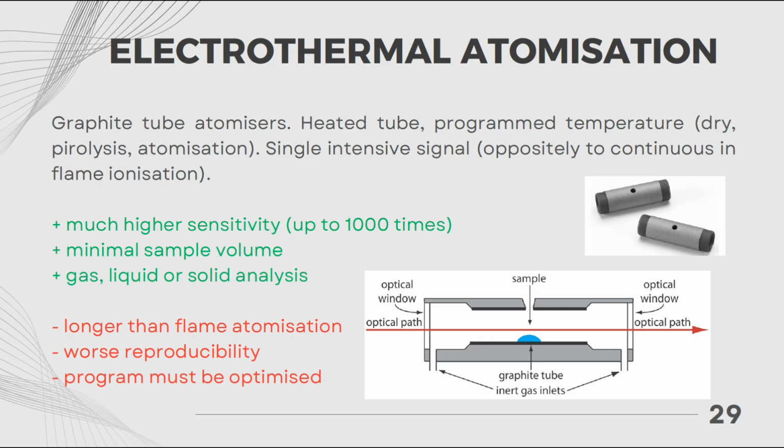So there is no flame. Atomization is performed with this highly heated tube. And because atoms stay longer in the chamber, in this tube, it leads to much higher sensitivity, indeed up to 1000 times increased sensitivity, which is excellent. The increase is very noticeable, just because you measure the same analyte for a longer time.